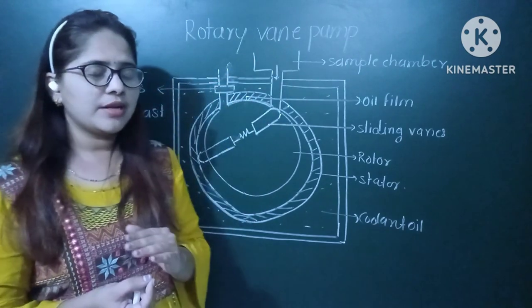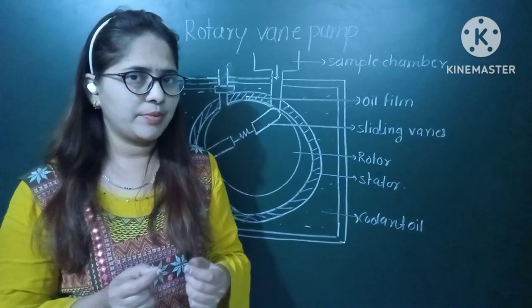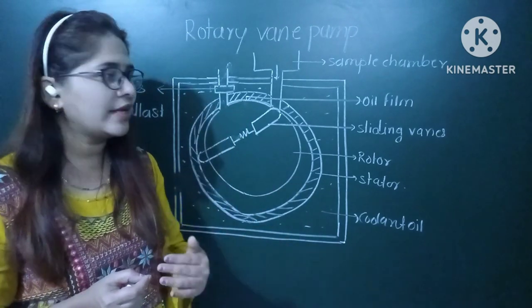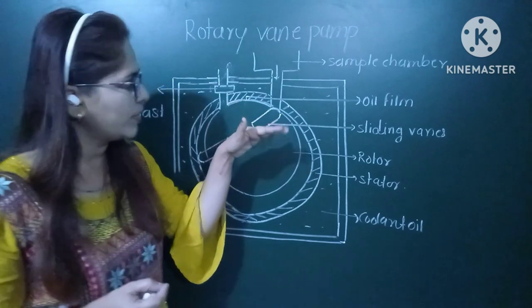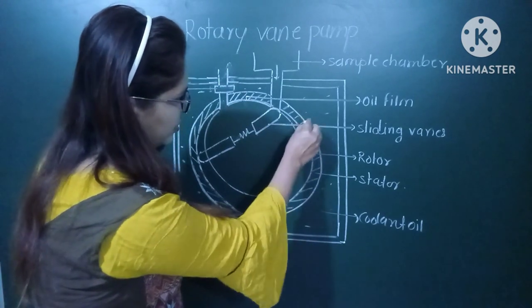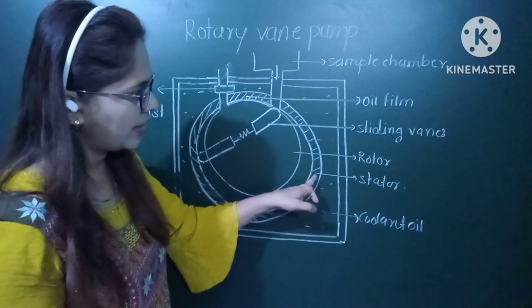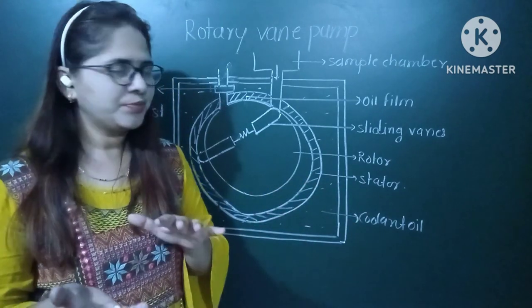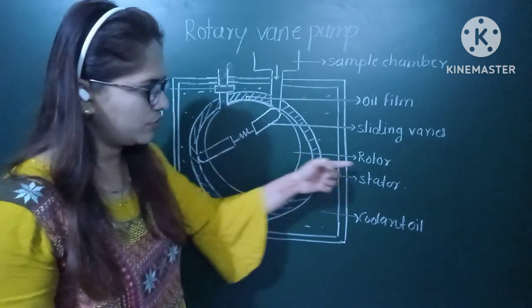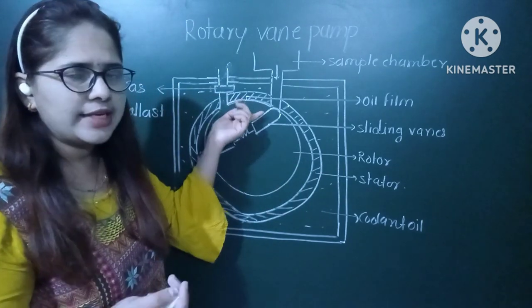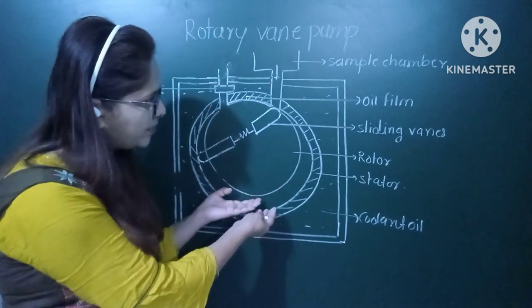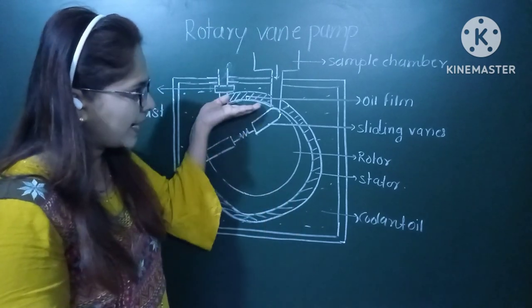This rotary vane pump comes under the positive displacement pump. In the positive displacement pump, we remove the air molecules mechanically from the sample chamber. This rotary vane pump consists of a stationary part called the stator, which remains stationary. To that stator, one rotating part called the rotor has been connected eccentrically. Eccentrically means this rotor is not present exactly at the center of the stator — it is placed eccentrically.